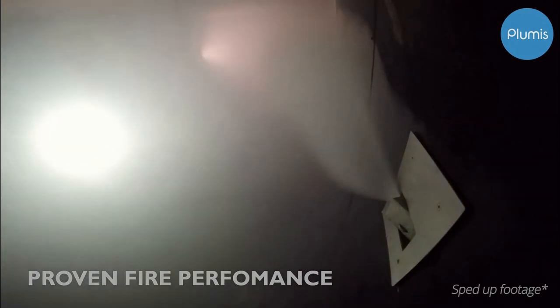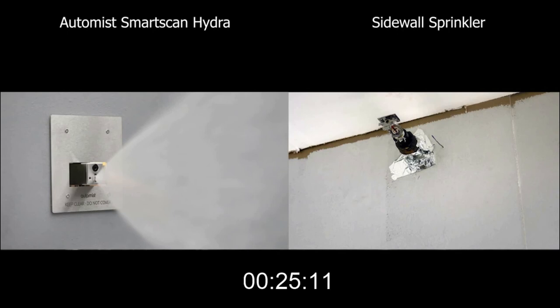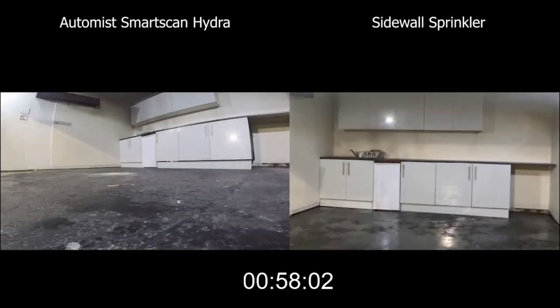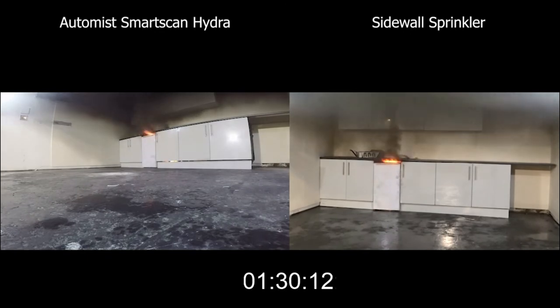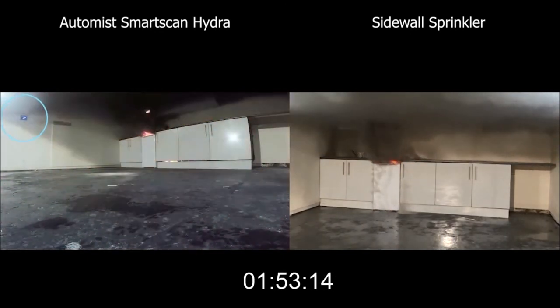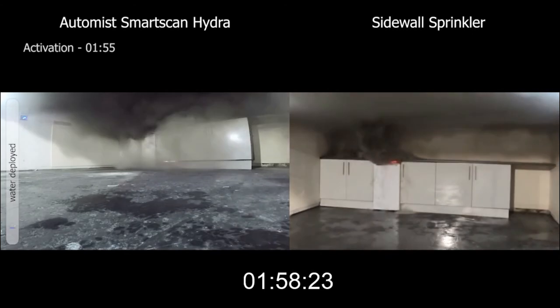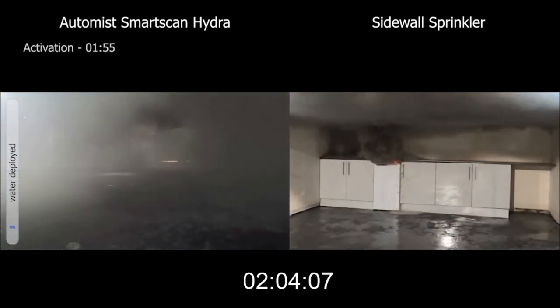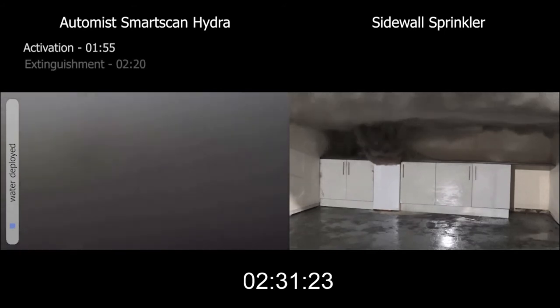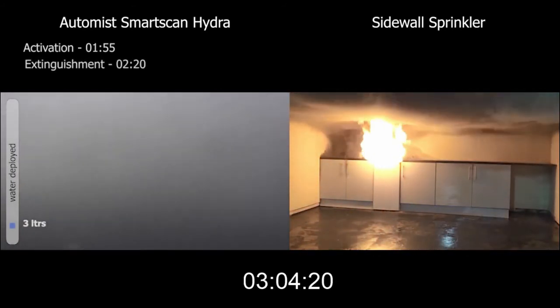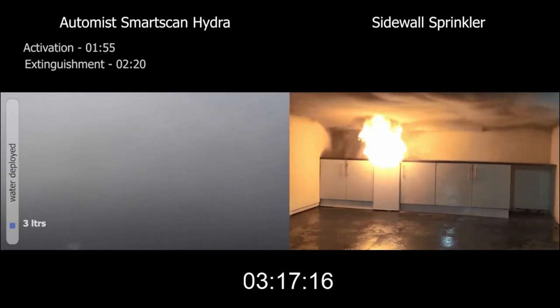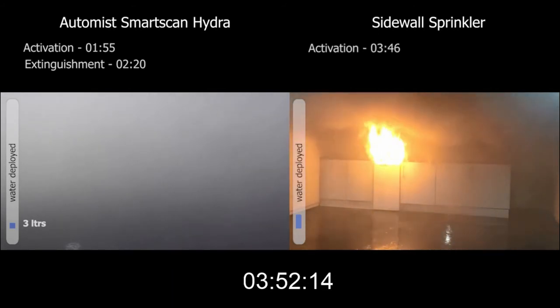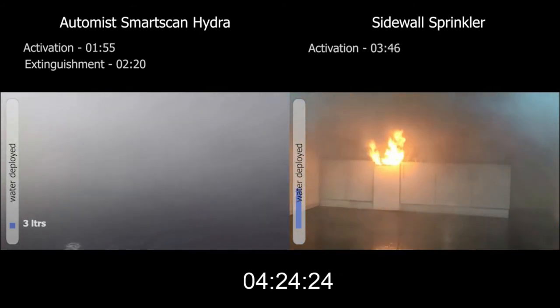Now, we've tested it against the fire performance in BS8458. What you'll see here is the benefit of our approach on this particular type of fire. And you'll see in the room protected by Automist, we get activation approximately 2 minutes before the residential sprinkler. We're able to put out that fire with 3 liters of water, whereas with the traditional system, it took considerably longer and approximately 80 liters of water. Limit that amount of consequential water damage.